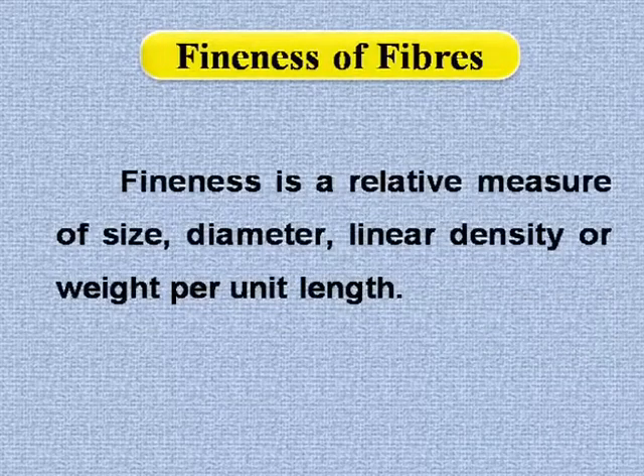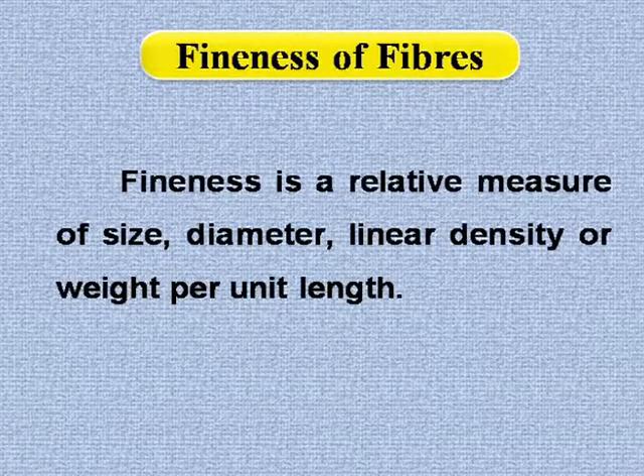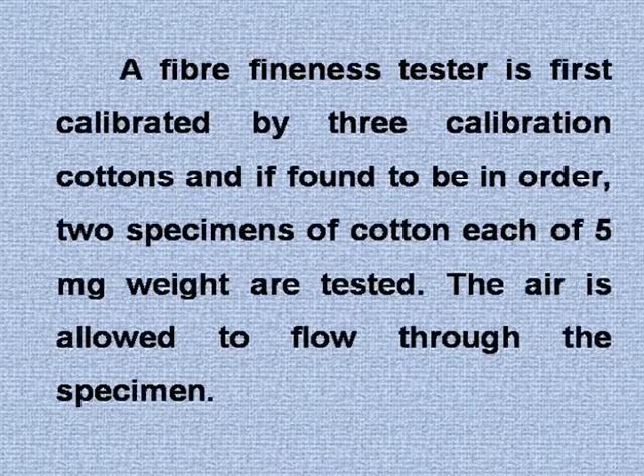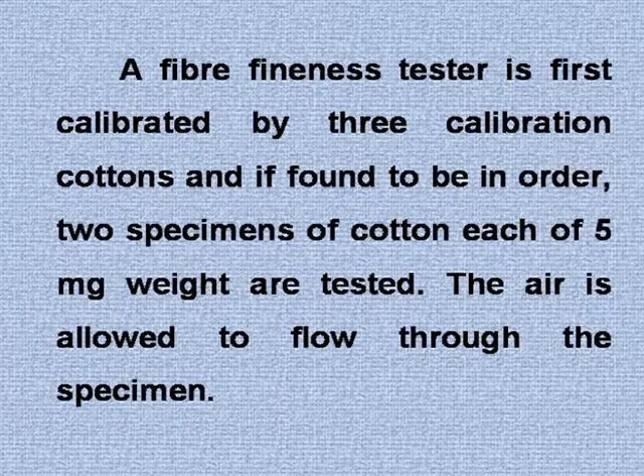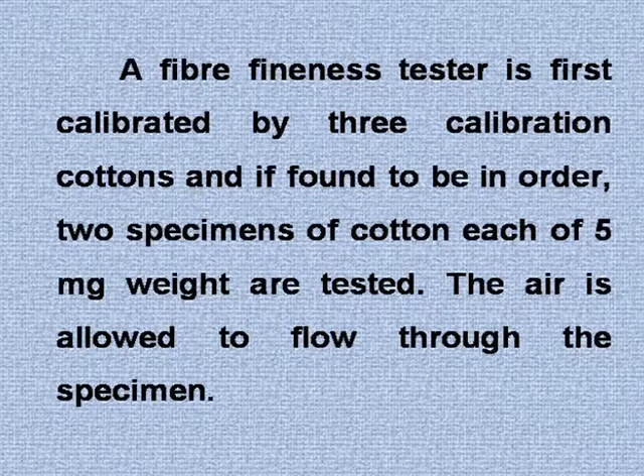Fineness is a relative measure of size, diameter, linear density or weight per unit length. A Fibre Fineness Tester is first calibrated by three calibration cottons, and if found to be in order, two specimens of cotton each of 5 mg weight are tested.